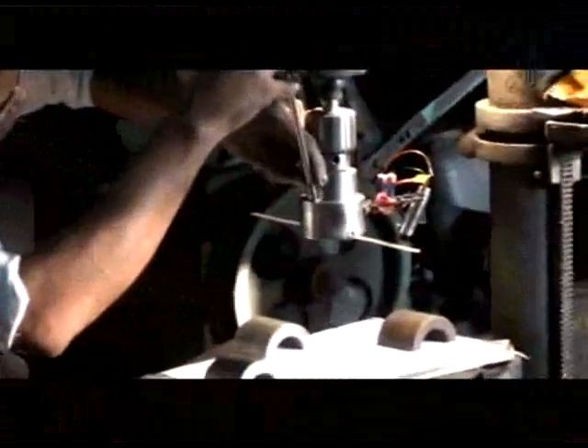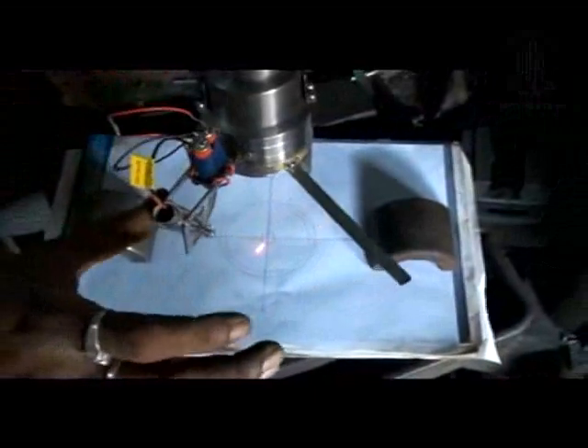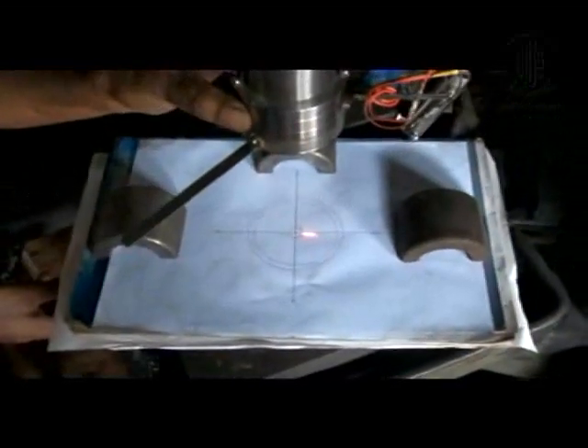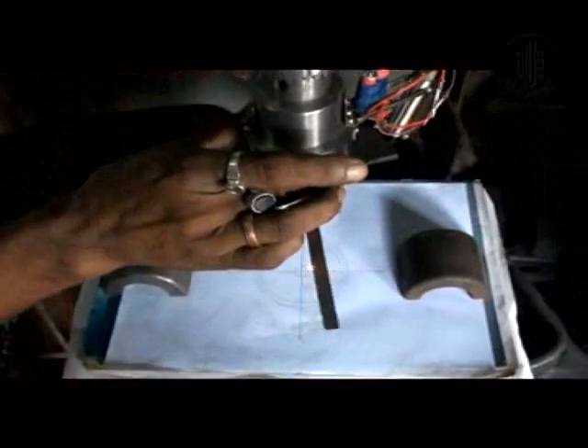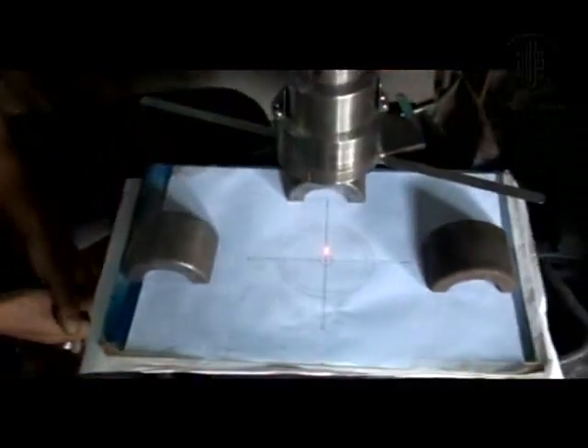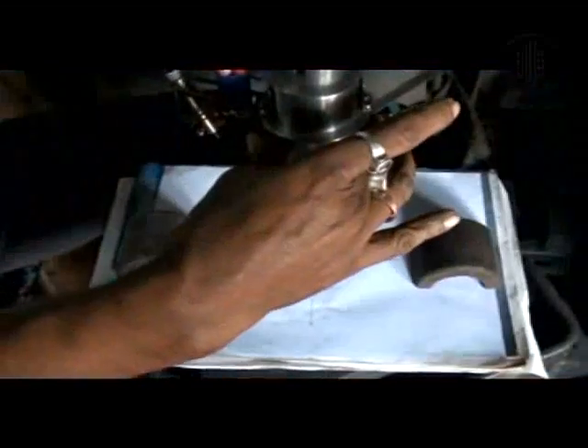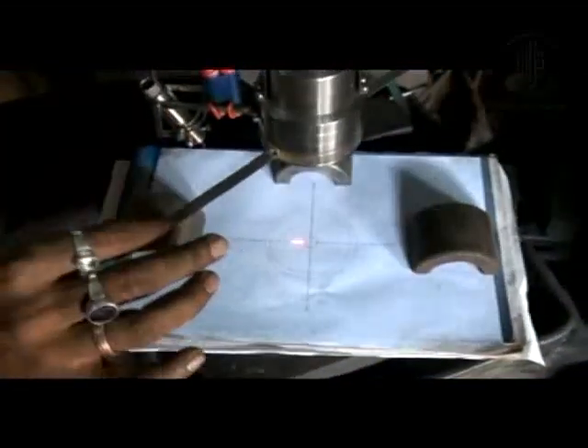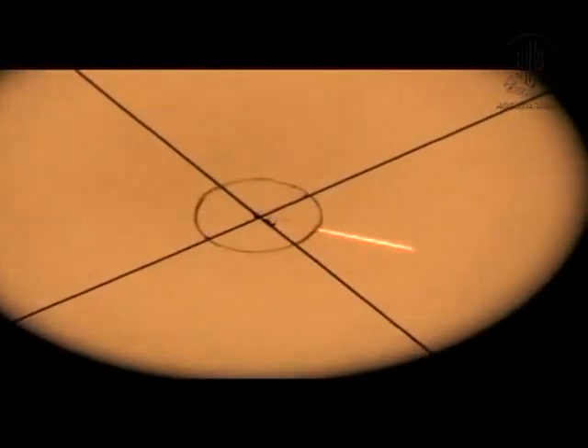The accuracy and calibration of the instrument was tested previously by fitting it onto the chuck of a vertical drilling machine. The center was marked on a piece of paper beforehand. An 11 mm diameter circle was drawn on it, resembling the limbus, with 2 lines passing through its center, the horizontal and the vertical axis. Line laser light was projected on the piece of paper and rotated to see whether the lights are falling on the 4 lines. The line laser was once more calibrated in the operating room prior to surgery.